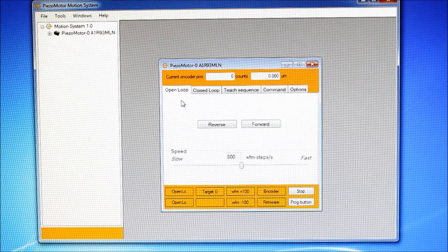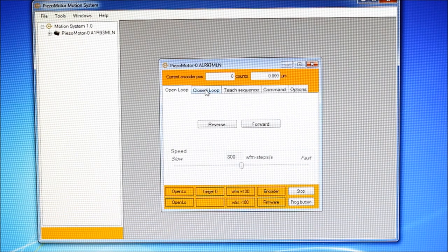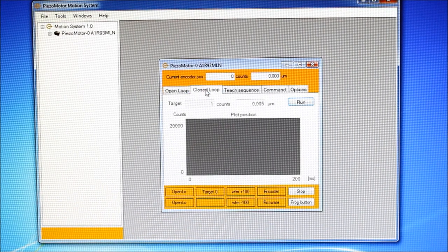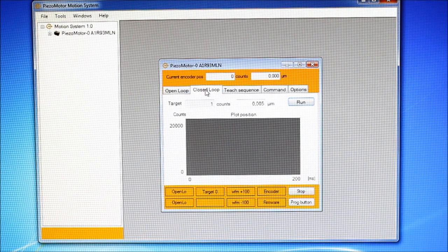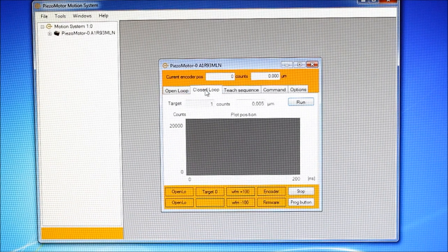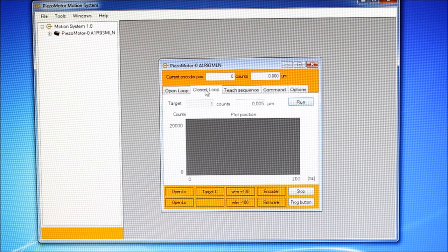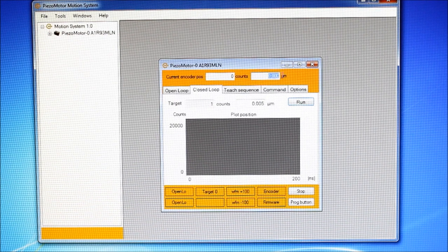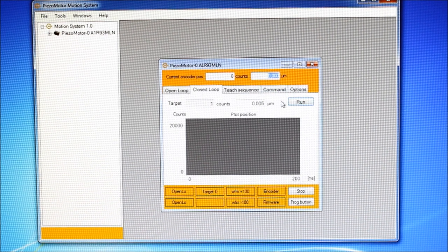Let us run in closed loop. The microstep driver uses encoder readings to smoothly reach a target position. Here you can see the actual encoder reading.